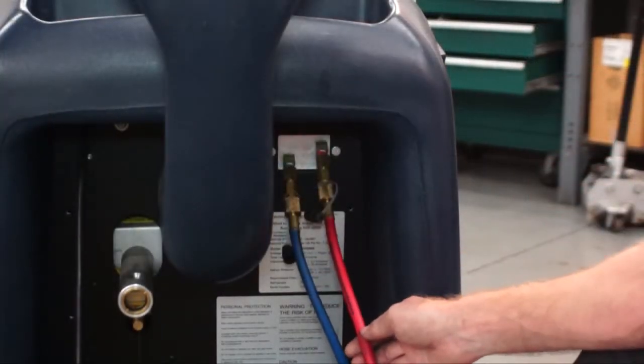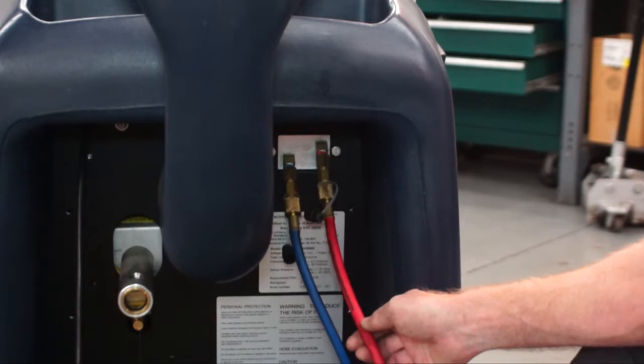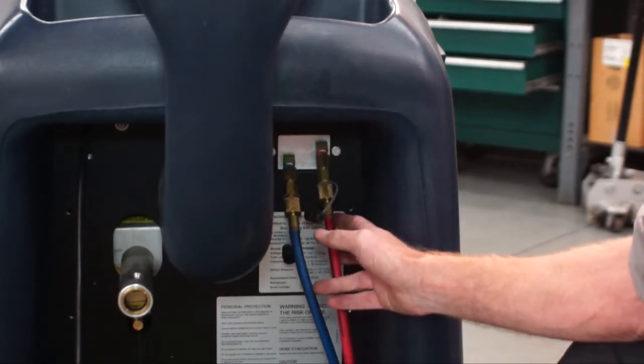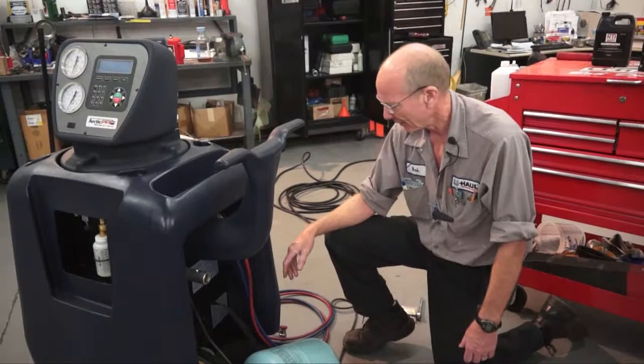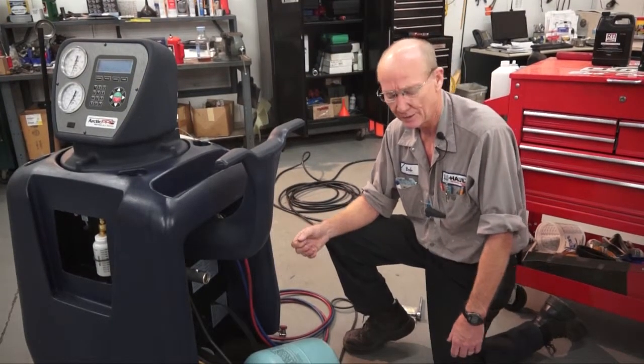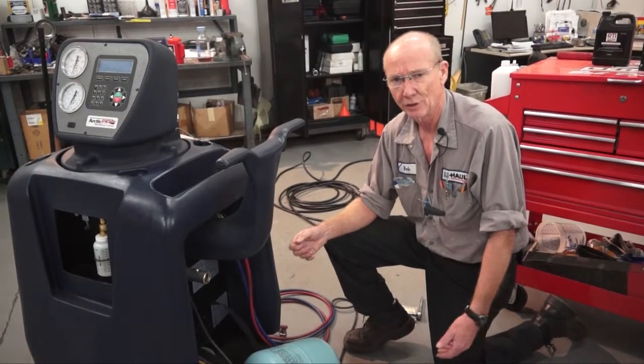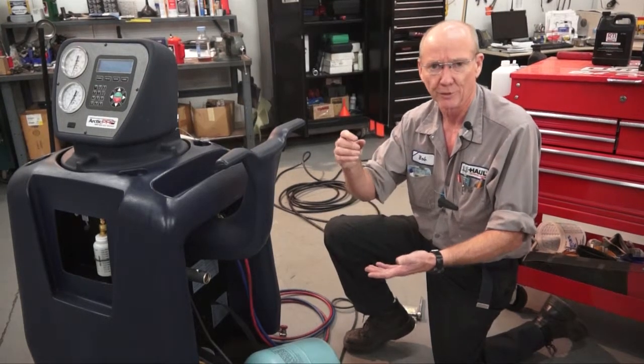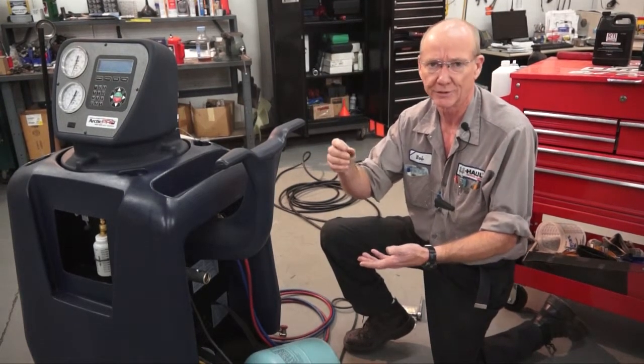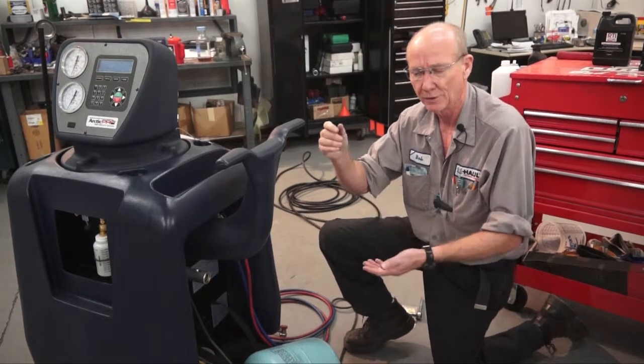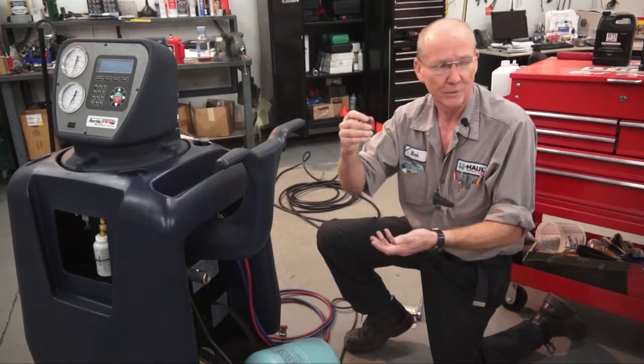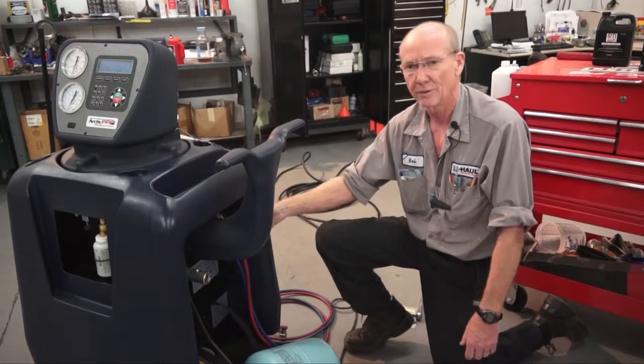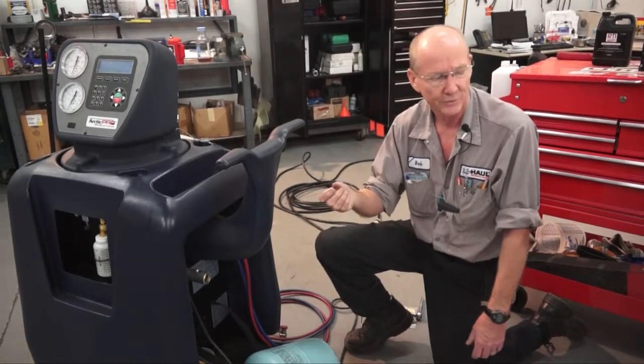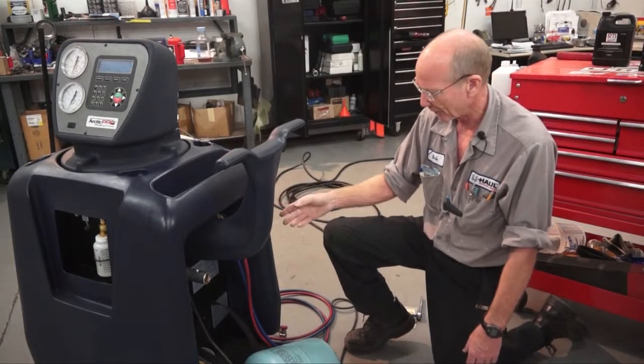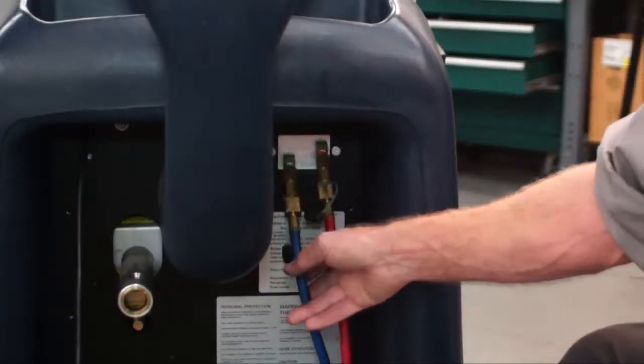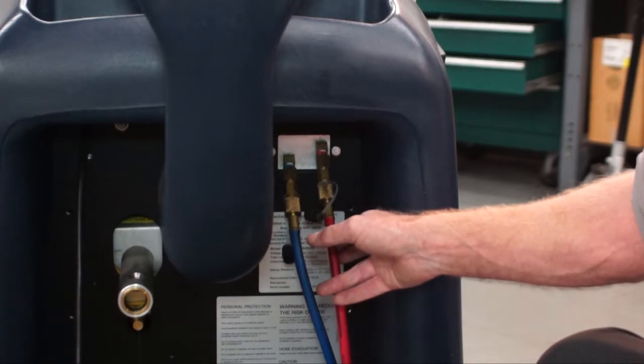You'll notice more of the contaminant will be on the filter on the high side. The reason for that is where the service ports are located. The low side service port is located on the accumulator, up kind of out of the way of the oil. It's suspended up. The oil's in the bottom of the accumulator, and it's recovering mostly refrigerant. On the high side, you're recovering a lot of oil and refrigerant because of where the service port fitting is located. So you'll probably notice a lot of the time that the inline filter on the low side is much cleaner than the high side.